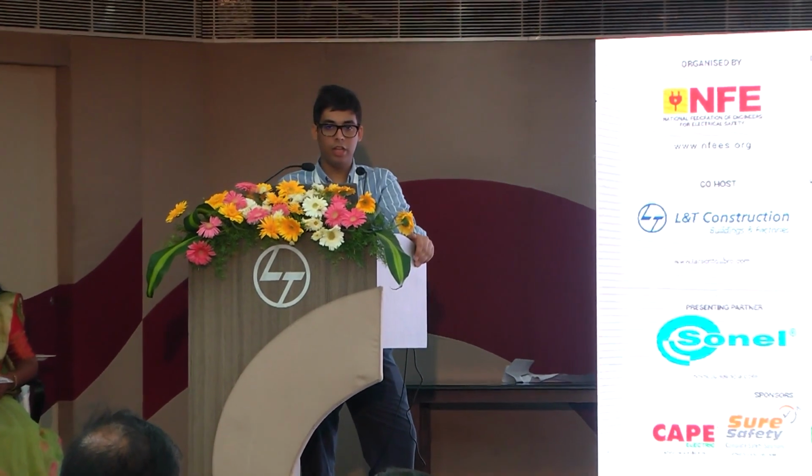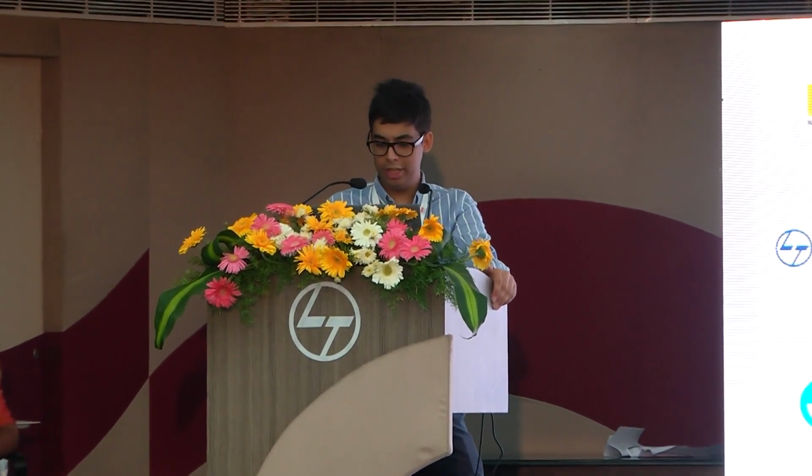Another important thing is, like I said, when sunlight or UV radiation is present, this will have one effect on the insulation, but it will also have an effect on increasing the operating temperature. So derating is required. Now, what factors are these? Let's look into this a little further on.